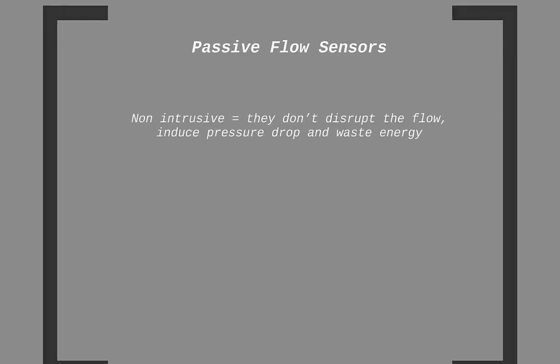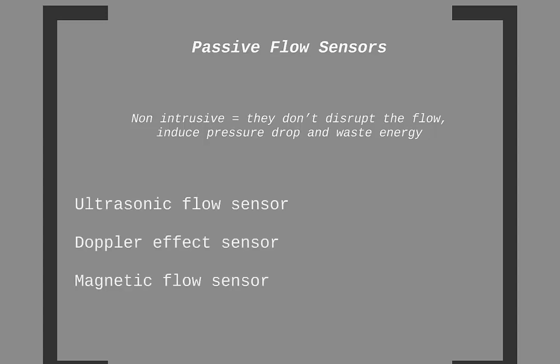All the flow sensors we've discussed thus far require installing junk into the flow stream path. That junk creates frictional losses, which results in the pump or fan having to work harder and burn more energy. There are some options of flow sensors available that can take away such obstructions from the flow stream. These are termed passive flow sensors. Some options we have there are the ultrasonic flow sensor, the Doppler effect sensor, and the magnetic flow sensors. We will not go into the science behind these, but you do see them at times in HVAC systems.